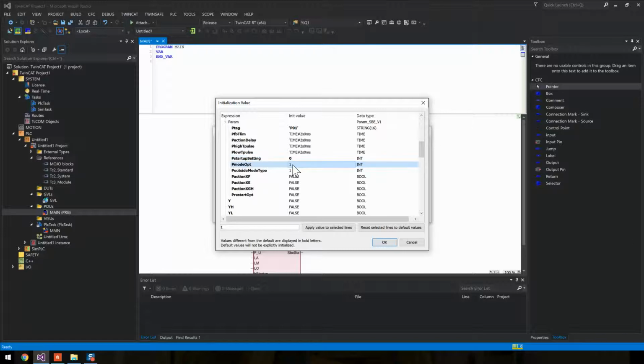Mode options should be which modes are available, and I'm not sure which option says all 3 of them. So let's figure these 2 out first. Here are some delays. If you don't get the feedback that it's actually running when you want it to run, within 2 seconds there's an alarm. And if you lose the feedback, there's an alarm after 2 seconds.